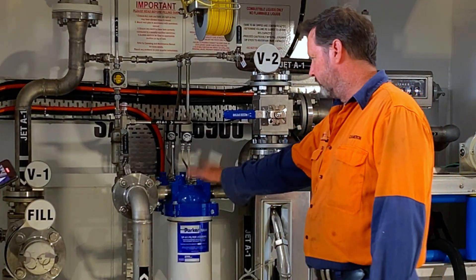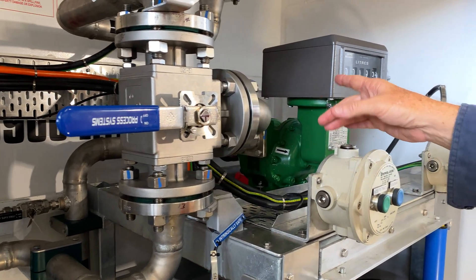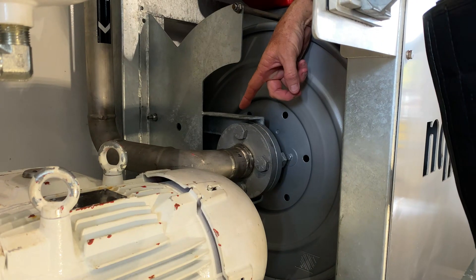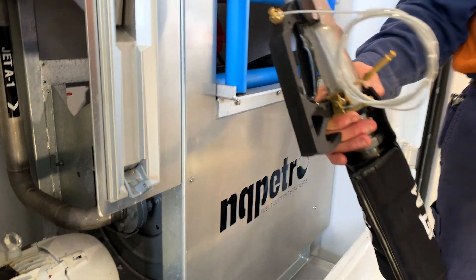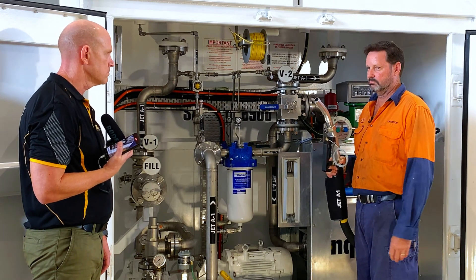Fuel comes through here, through the filters again, through this valve — which has been changed in direction — so it's now coming up through the meter, out of the meter, through a flow control valve and into this hose reel, through the hose reel and out to a nozzle. The pilot can then take that out to the aircraft, turn it on, and fill his fuel.